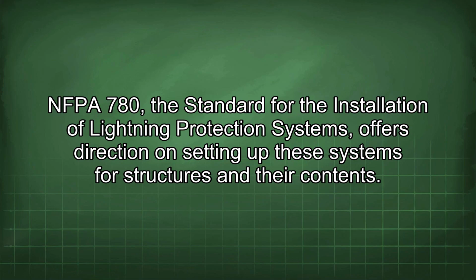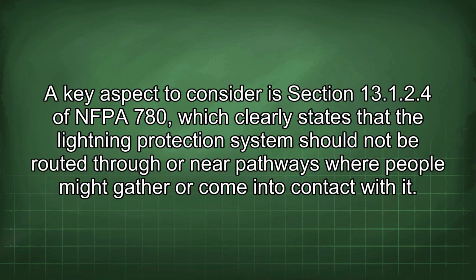NFPA 780, the standard for the installation of lightning protection systems, offers direction on setting up these systems for structures and their contents. A key aspect to consider is Section 13.1.2.4 of NFPA 780, which clearly states that the lightning protection system should not be routed through or near pathways where people might gather or come into contact with it.